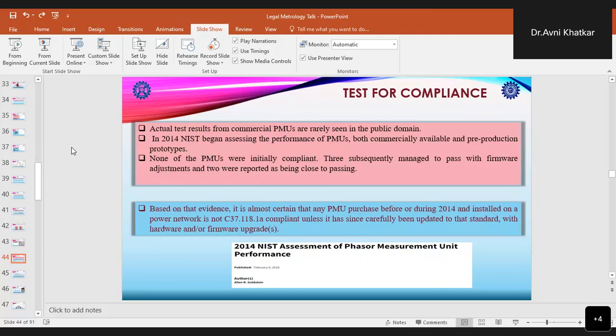So based on this evidence, it is almost certain that any PMU which was purchased before or during 2014 and installed on the power network is not compliant with the IEEE standard, unless it has been carefully updated to that standard with hardware or firmware upgrades. This information is available in the public domain in the form of the report published by NIST, and it provides a number of insights into PMU behavior. However, it is restricted in showing only generalized results in order to maintain manufacturer confidentiality.